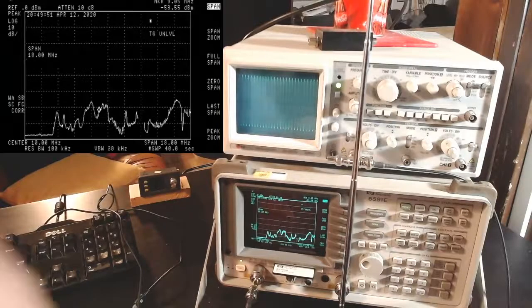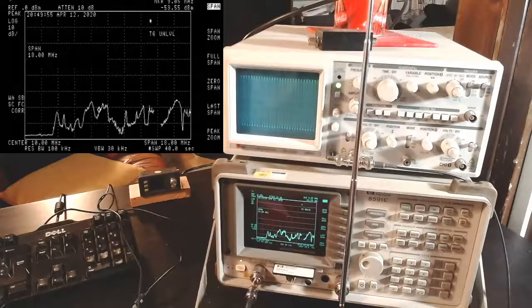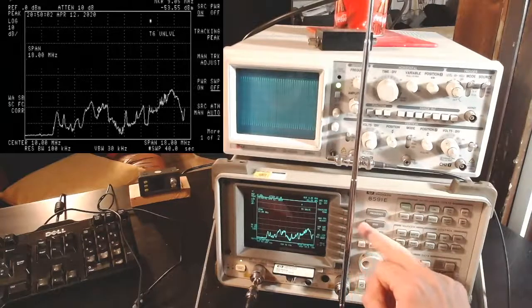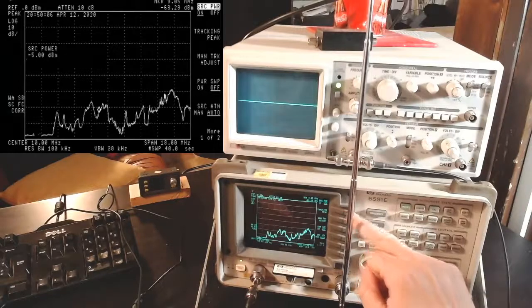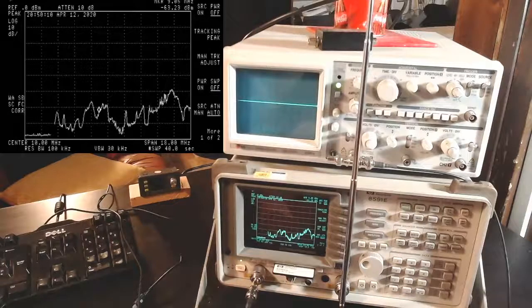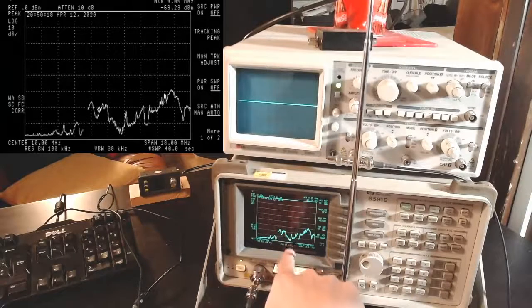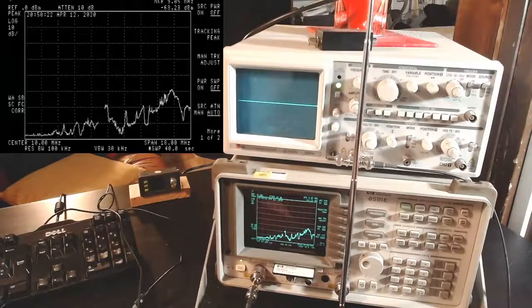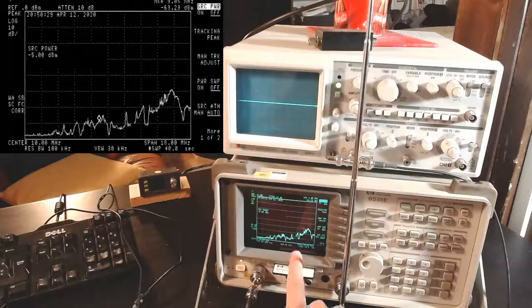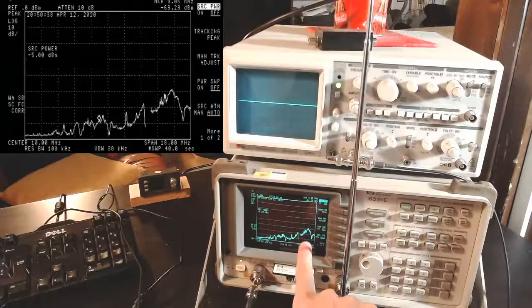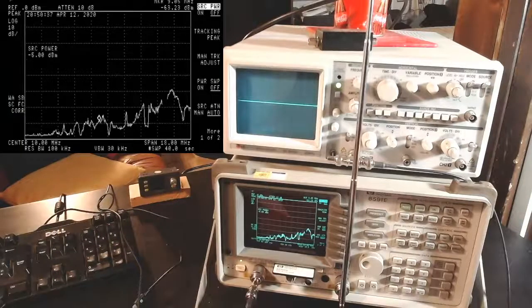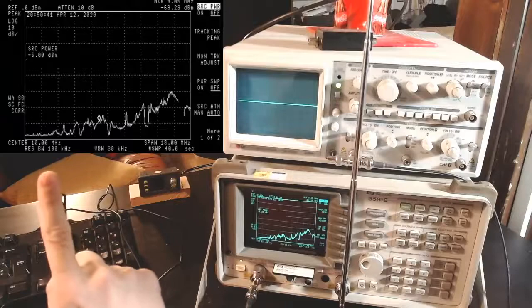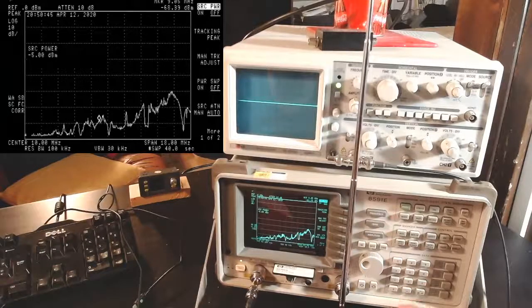And as you can see, we get a wave. So let me actually check here. For a second, let's turn off the tracking generator, which is simpler. So the tracking generator now is off. Still, the spectrum analyzer is working just as before, but the output is not enabled. Okay. Now we can decide instead to enable it, and we can do that. The signal that will be output, following my finger, so following the intermediate frequency of this spectrum analyzer, will have a certain power. Now the power is set to minus 5 dBm. Let's put it in fact to minus 10, so a bit lower.